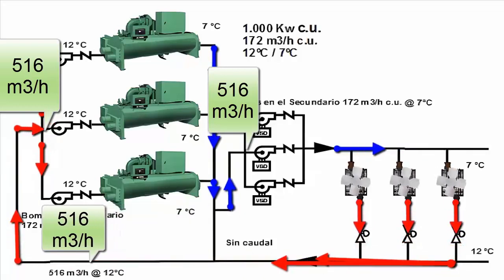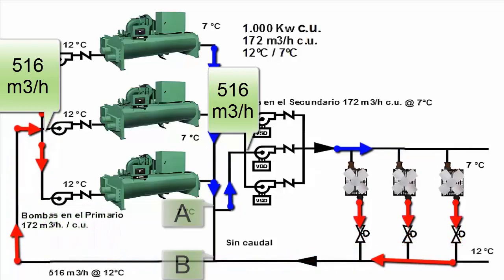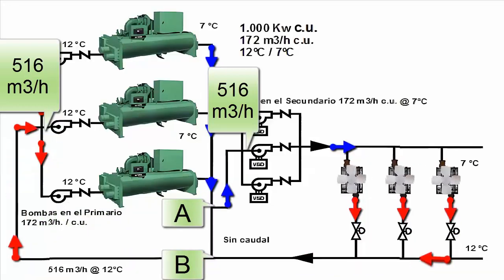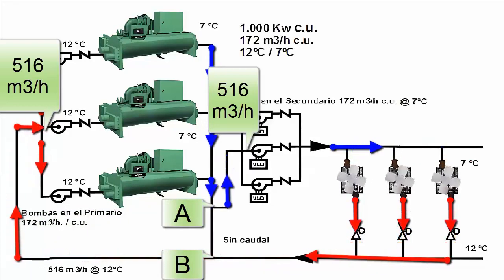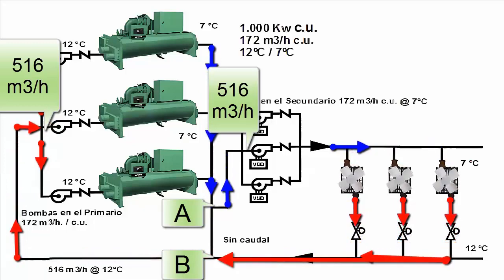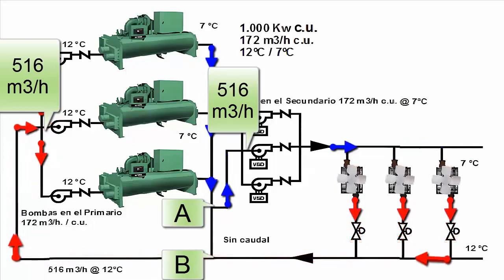The part from point A to point B is a connection that, in this case, has zero flow, as all the water leaving the chillers is directed to the building, and there is no excess chilled water.